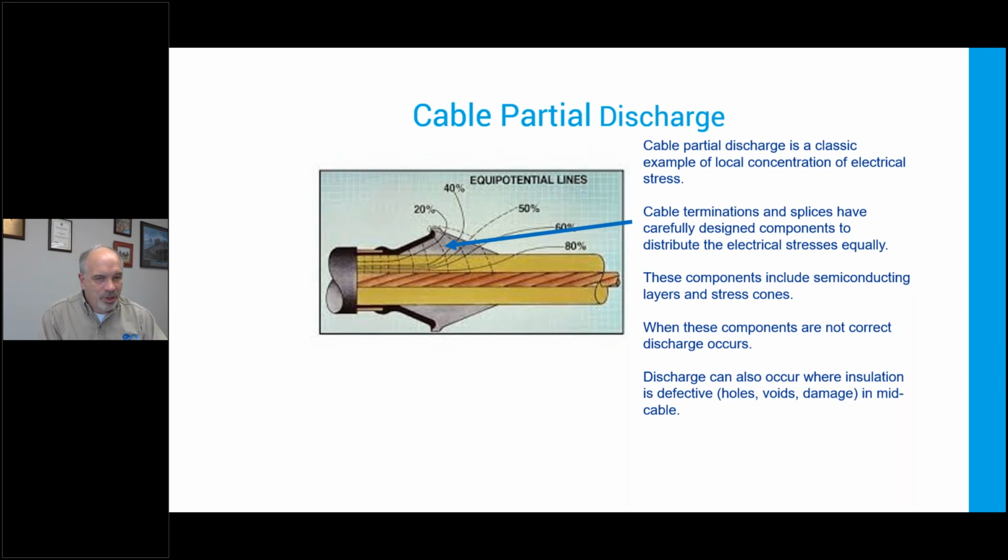But you get this discharge, and it's very often as a result of workmanship. You know, for those of you on the call that are cable joiners, it's not easy. You're asked to do something that requires hospital cleanliness in a trench, in the rain. So it's not anybody's fault. It's just hard to do. So you see a lot more problems in field terminations.